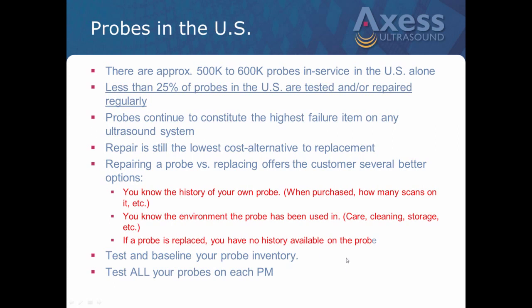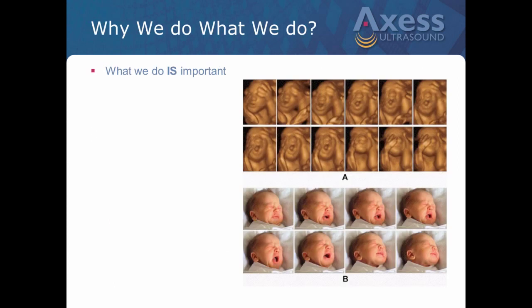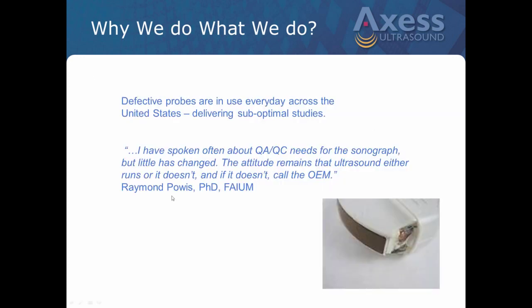The gentleman asked about the test devices. Again, if you have a probe inventory that's significant, a lot of ultrasound machines and probes, get a first call, and test and baseline your probe inventory. Test it at least once a year, if not a couple times a year. In some cases, when possible, test your probes on each PM. At the very least, when you're doing a PM, make sure you look at all the probes on the machine.